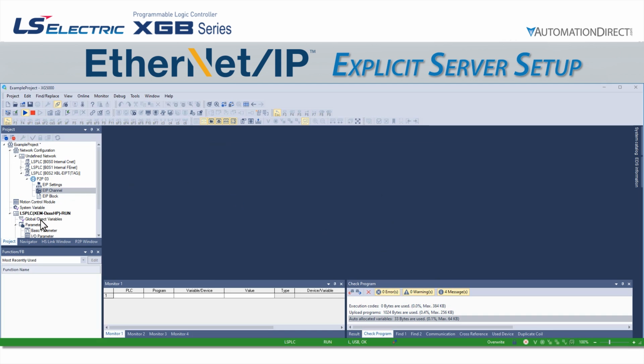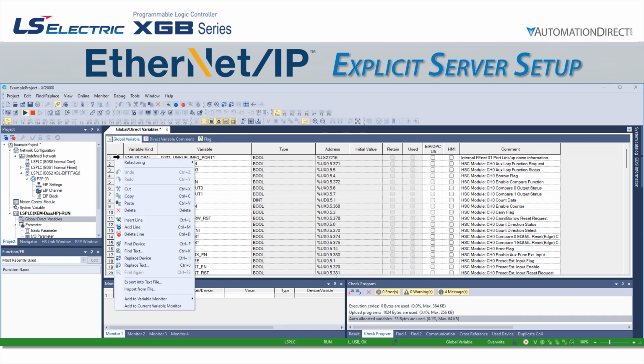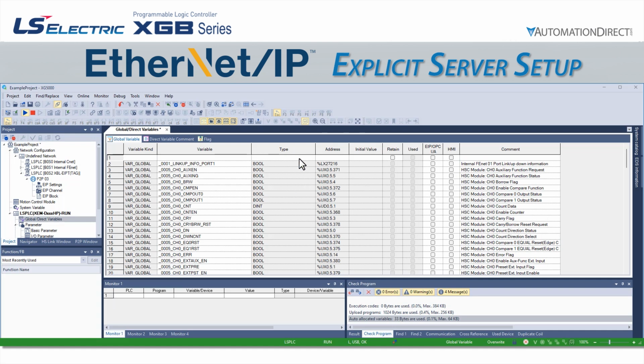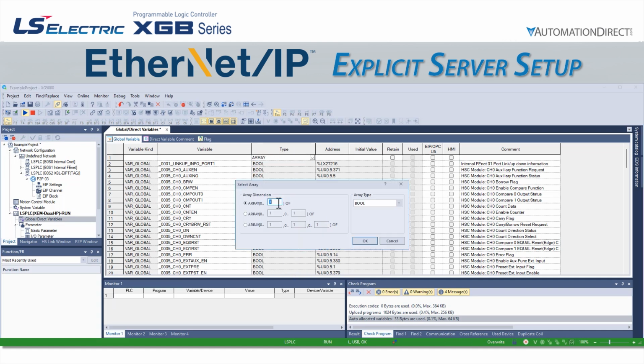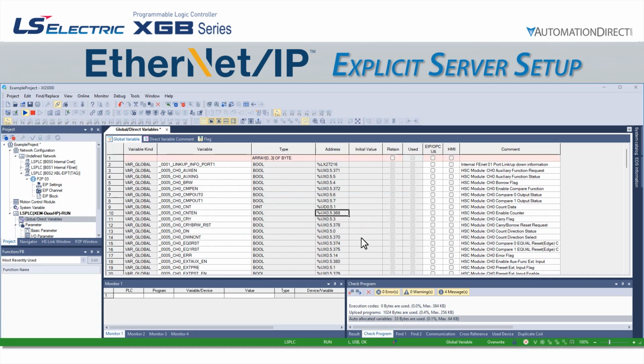We go to the Global/Direct Variable screen and insert a row. We can then create an array of elements 0 to 3 of data type byte, and we will name it EIP_server_data. This will be a global variable, and we will check the EIP OPC UA box to make the array available for use with Ethernet IP communications.